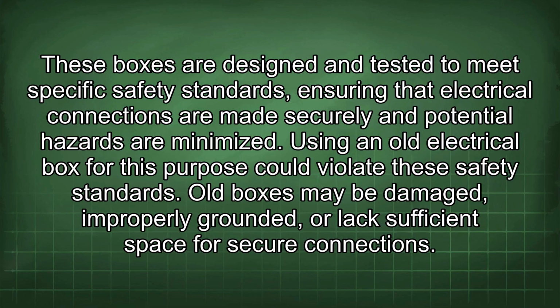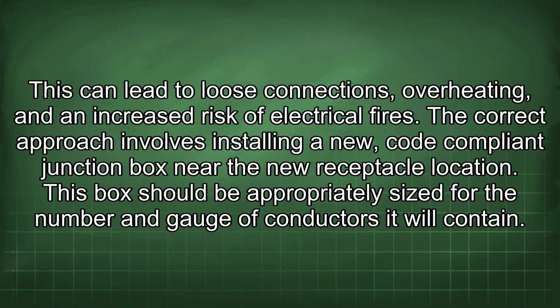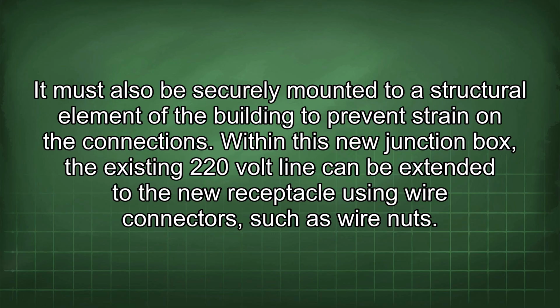Old boxes may be damaged, improperly grounded, or lack sufficient space for secure connection. This can lead to loose connections, overheating, and an increased risk of electrical fires. The correct approach involves installing a new code-compliant junction box near the new receptacle location. This box should be appropriately sized for the number and gauge of conductors it will contain. It must also be securely mounted to a structural element of the building to prevent strain on the connections.